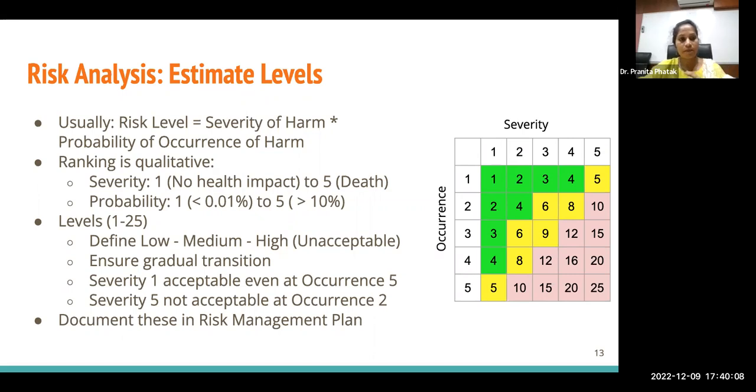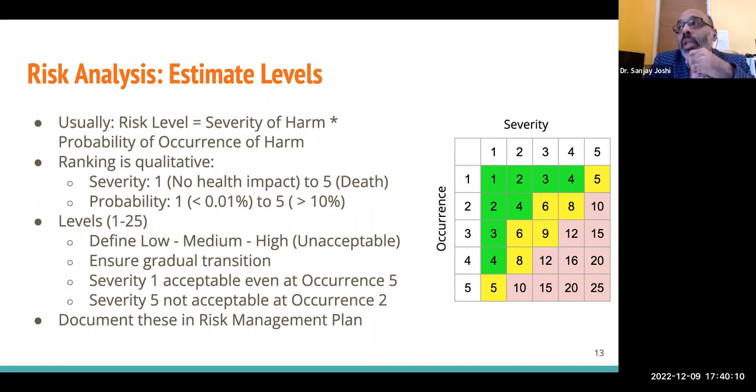Correct. So that's a great question. Mohini, let me rephrase the question. What you are creating effectively is a measuring device. It's going to give you either a yes or a no for the pregnancy, right? And I will still recommend, if you are going to market it as a medical device, you put the risk analysis here, and there are severities that you have to consider, which is what kind of harm could come when the device, in this case, it could be different kinds of hazard.